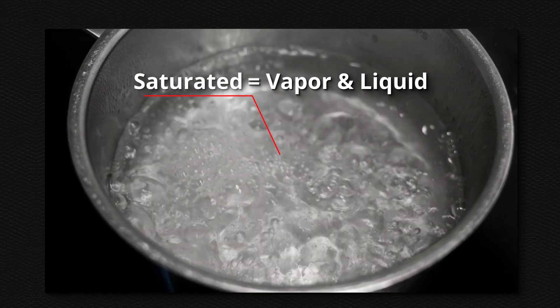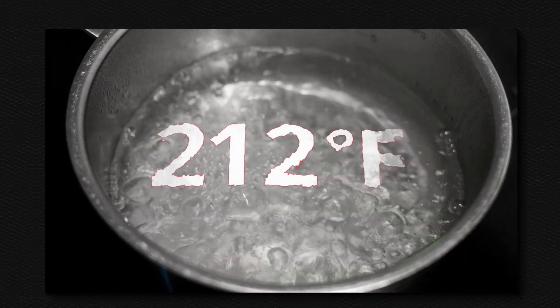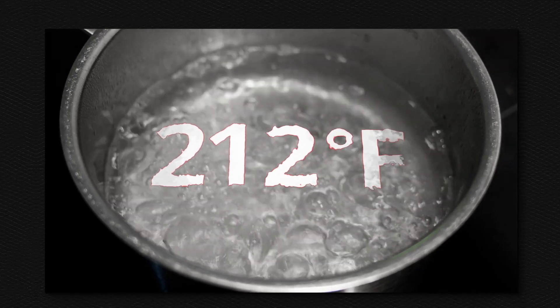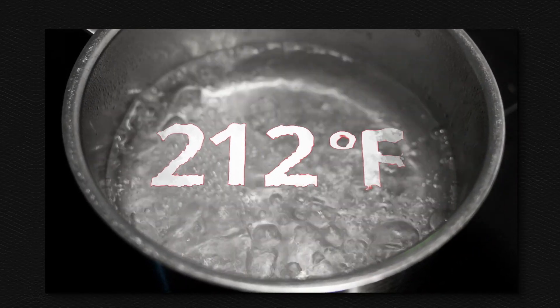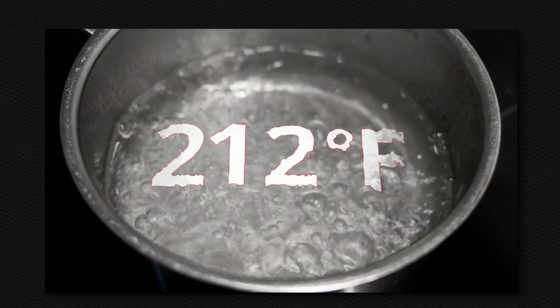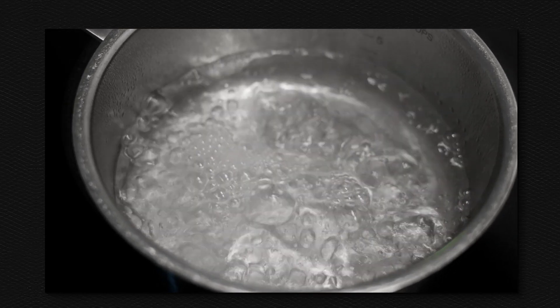As more heat is added, the water remains at the boiling point of 212 degrees Fahrenheit. The temperature of the water will not be above 212 degrees Fahrenheit while it is saturated. This is an example of what is happening inside the evaporator.